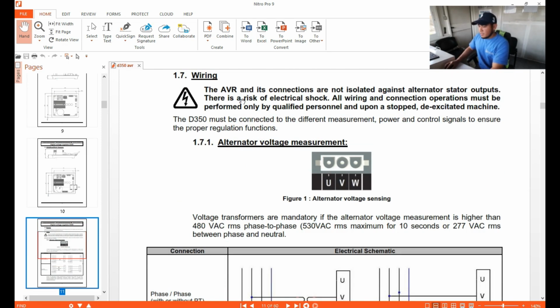Now the AVR's connections are not isolated against the alternator stator's output. Because of the risk of electrical shock, all wiring connection operations must be performed by qualified personnel. So if you are not qualified, do not attempt the wiring. But if you think you are qualified for this electrical wiring and installation, then go ahead. But take note, always follow the instructions and the wiring diagram for this kind of AVR, so you avoid wrong connections.